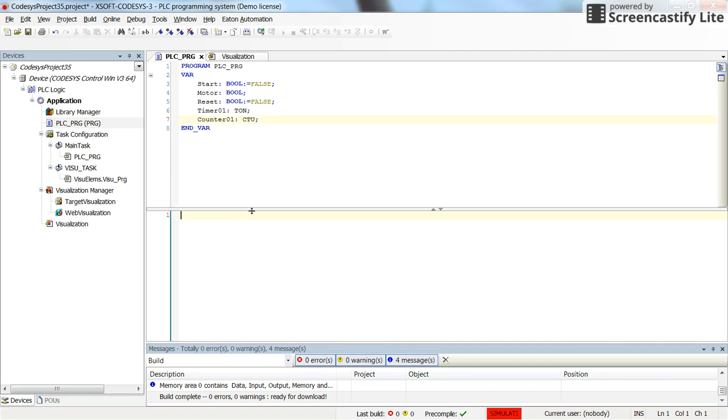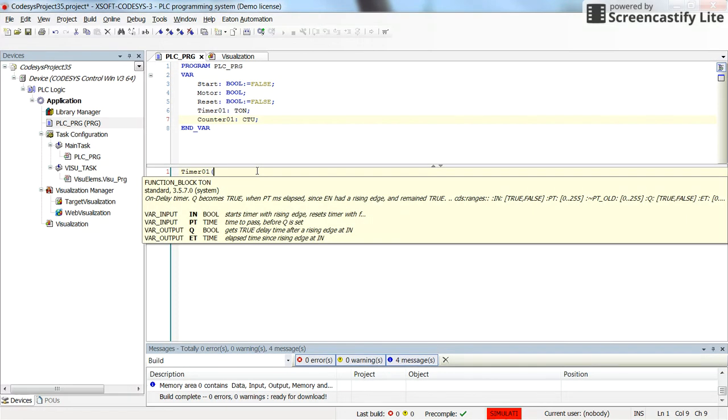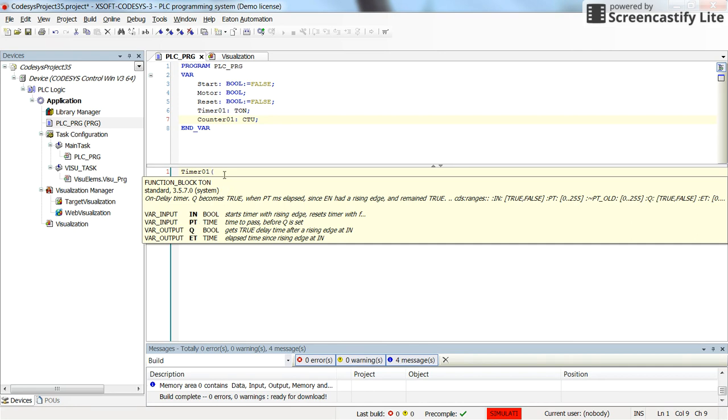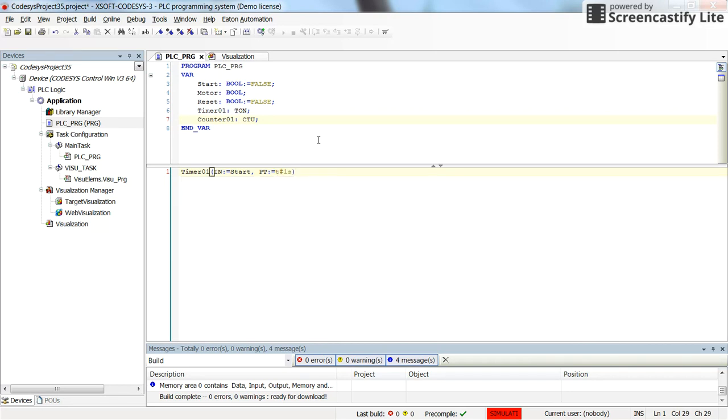Then here in the main body of the program, in the structured text programming, we can refer to timer01. And then open the parentheses and you can see here some hints. We have input variables as in and pt, and output variables are q and et. So I need to determine what is the input in terms of the in or whatever triggers the timer and the preset time. So for the in, I'm going to assign the start variable, and for the pt or preset time, I'm going to use t# 1 second. So this is how I am calling the timer01.